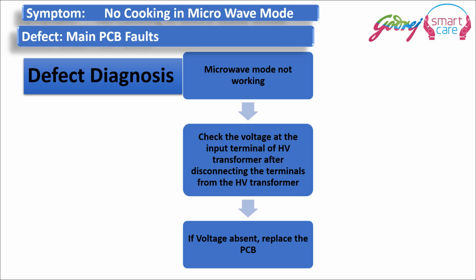We can check it only after disconnecting the input to the high voltage circuit, that is, the input to the transformer. The input to the transformer can be checked by the multimeter, to see whether the PCB is actually giving 240 volts to the input of the transformer and thereby to the high voltage circuit. But we have to remember that we should not touch the high voltage side when it is charged with voltage.